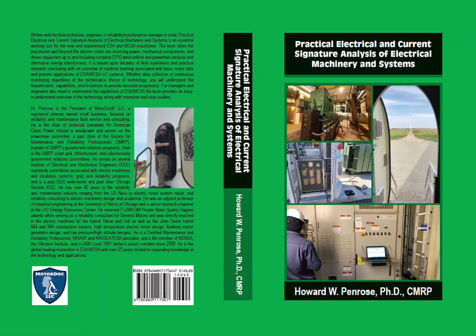Both were stating that there were rotor bar problems, and the repair sales department and repair managers had the motor out several times to demonstrate through a variety of means that the rotor was in good condition. The motor base was stiffened based on some observed conditions, and the motor was even sent to a manufacturer to load test for a cost of about $10,000. Our vibration phase analysis kept pointing to the base of the compressor itself from the first day on site, as did a subcontracted third party.